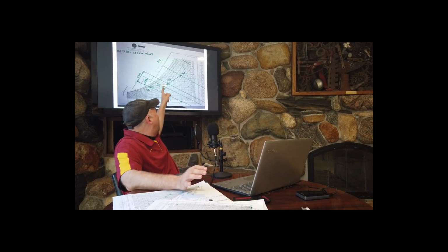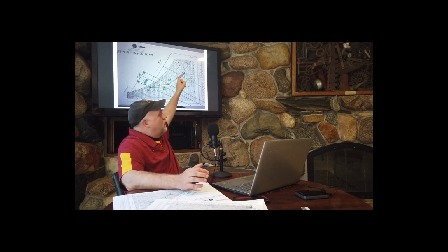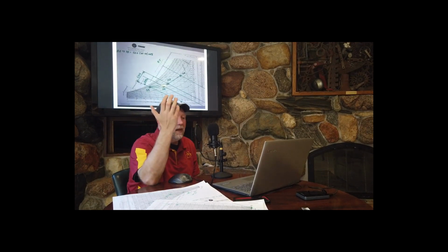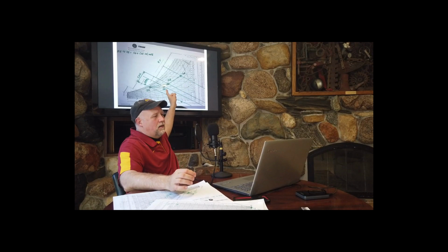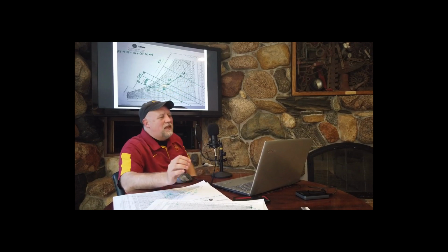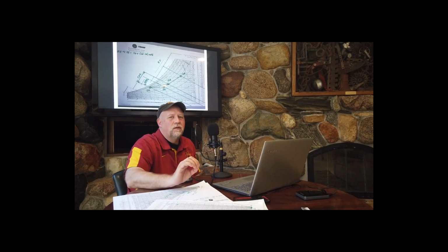If it was a house and we didn't bring in any outside air, well, down here. If this was a lab space and we were doing a 100% outdoor air unit, or maybe a kitchen, that air would be up here. But for most buildings, offices, schools, those types of normal buildings, we are going to mix some outside air with a bunch of return air. Where this is at, this is that whole percentage I told you.